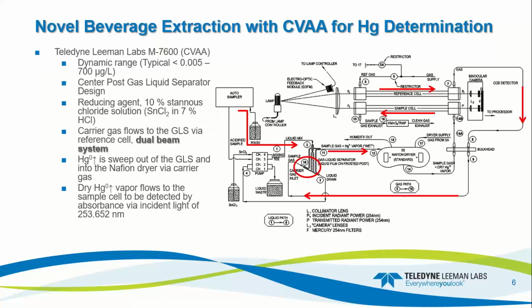So the 7600, this is a cold vapor atomic absorption system. The dynamic range is 5 ppt, 0.005 to 700 micrograms per liter. It's got a center post design for the gas liquid separator. Typical reducing agent is 10% stannous chloride and 7% hydrochloric acid. The carrier gas flows to the GLS through the reference cell. So this is a dual beam system.